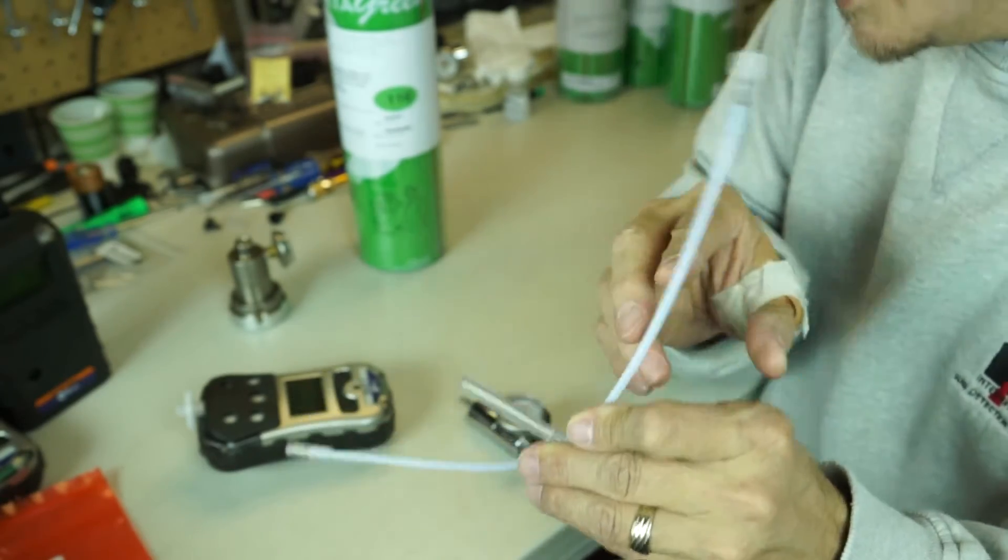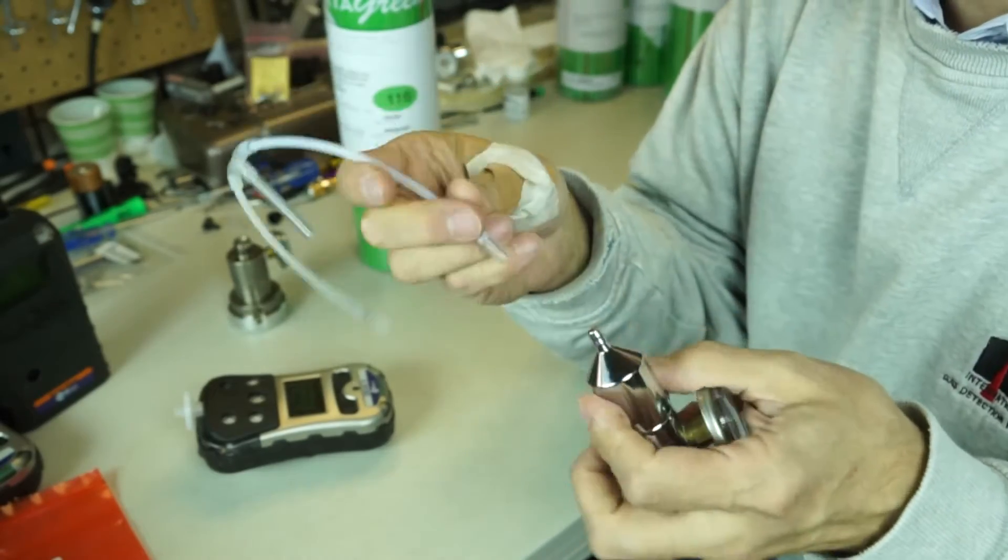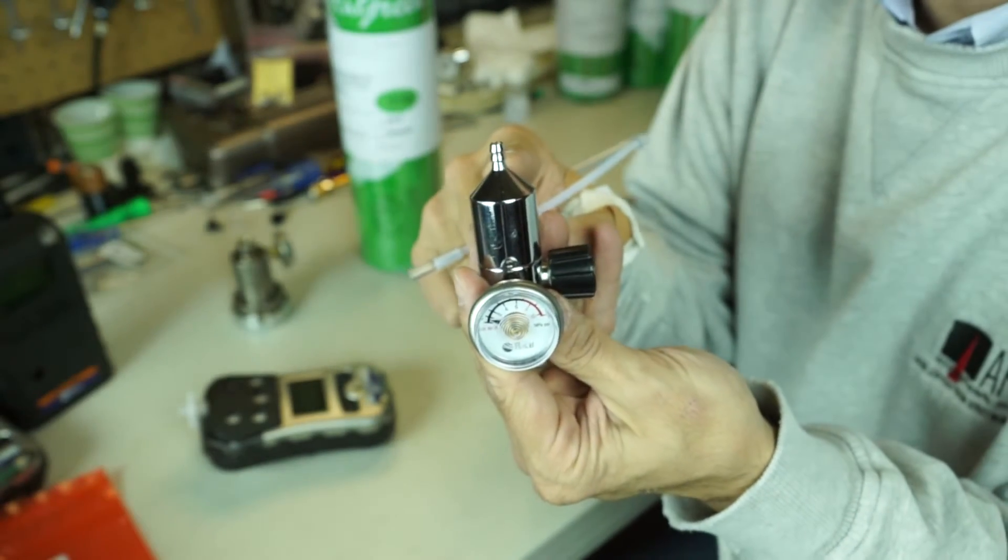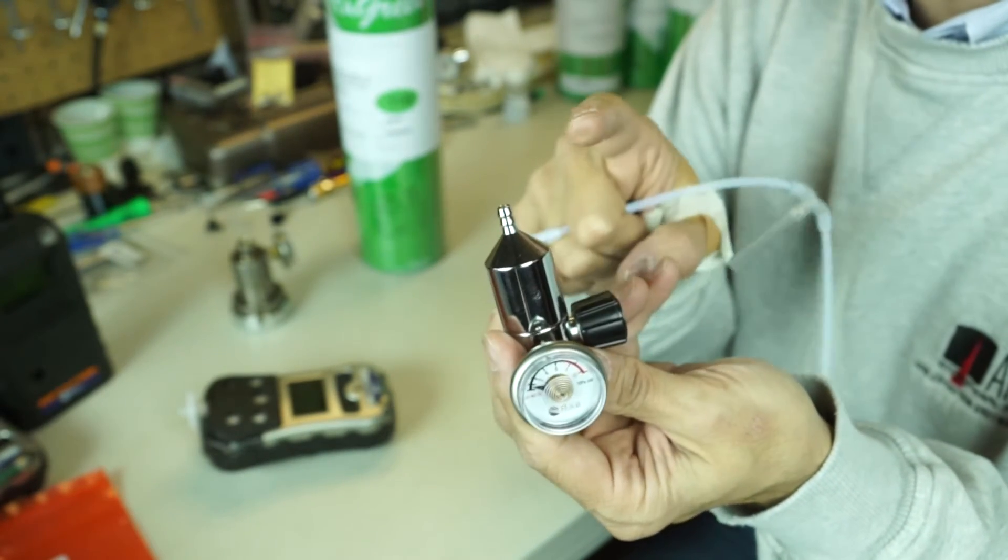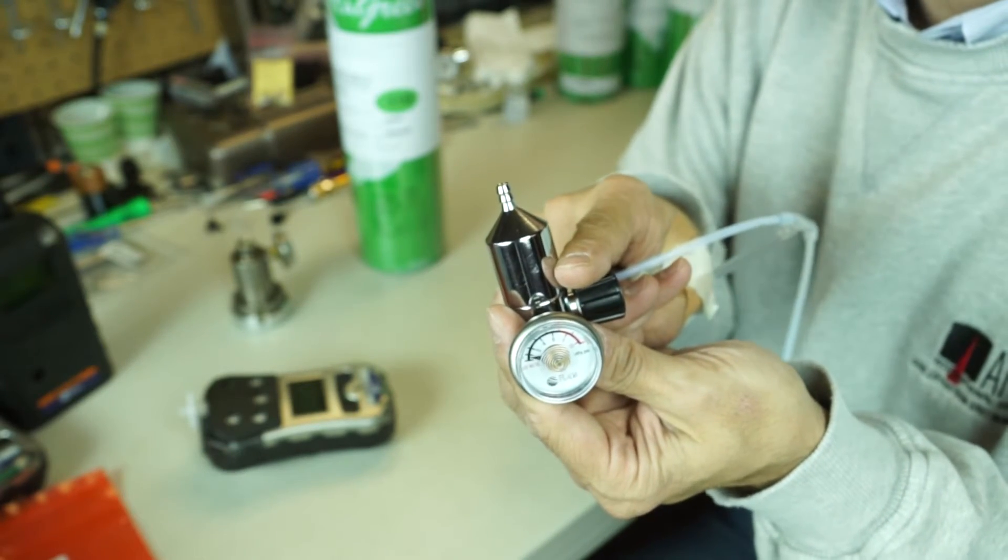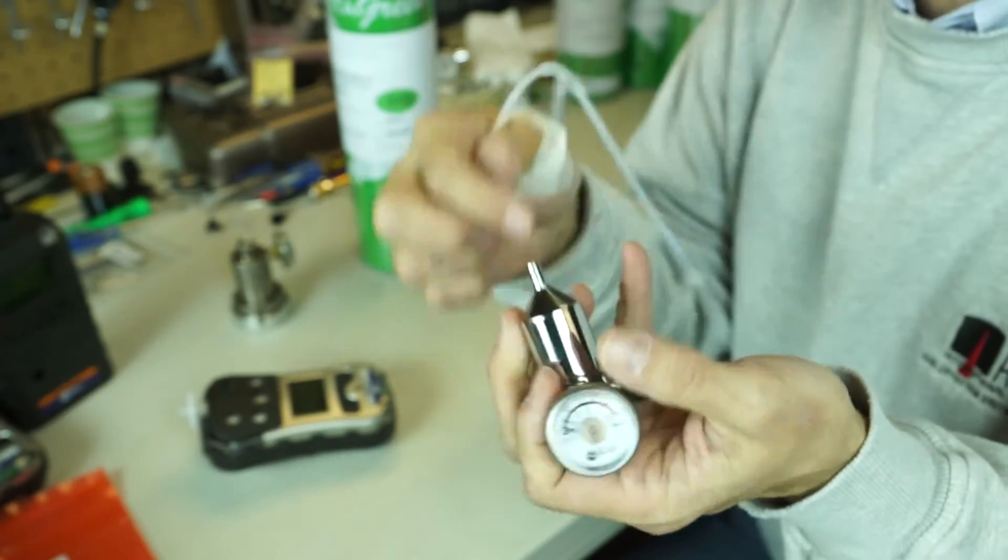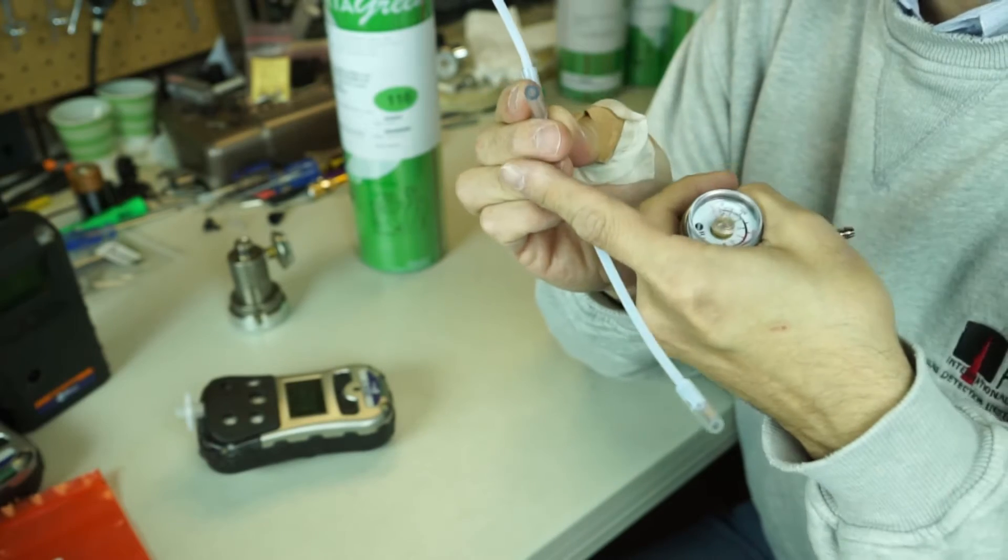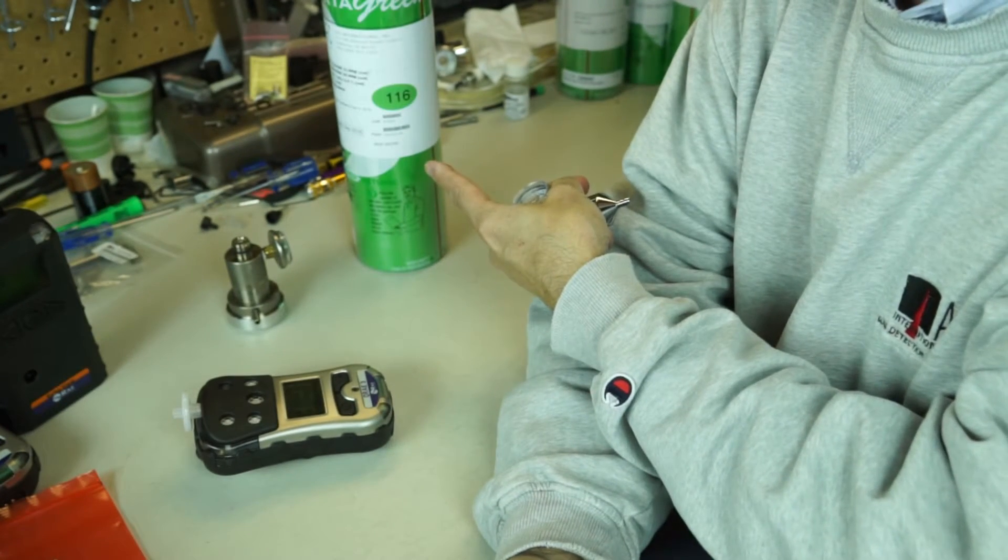So what I'm going to do here is I'm going to go ahead and connect up the instrument or the calibration T to the regulator. This is a fixed flow regulator from RAE Systems. And the key thing here is you got to make sure you use a regulator that has a flow that's greater than the draw of your instrument. If this regulator doesn't have a draw or a flow greater than the instrument, well then the third leg of the T is going to act as a dilution probe, and that'll reduce the gas concentration that we have in the cylinder.